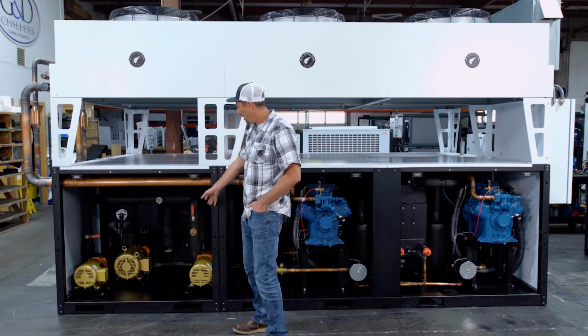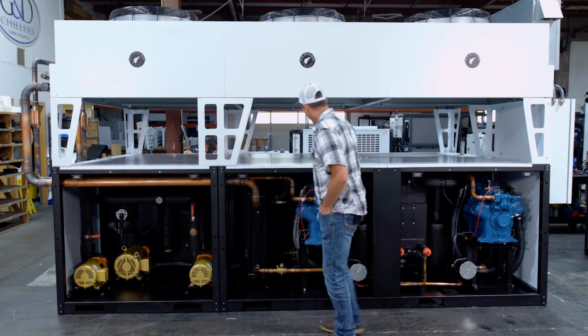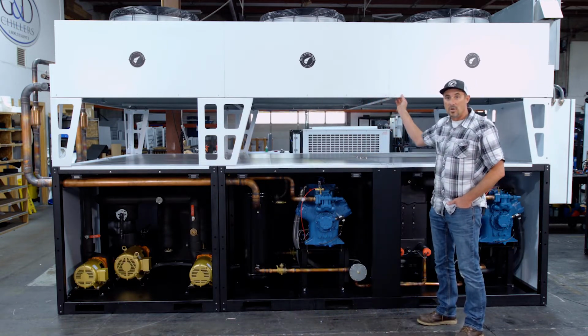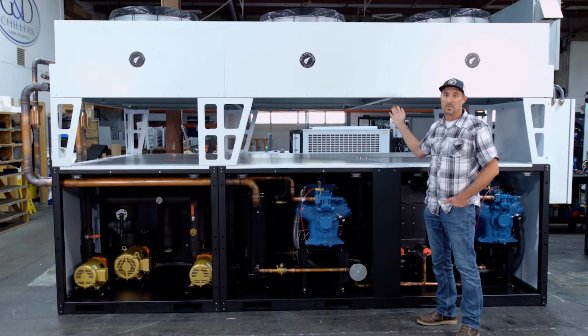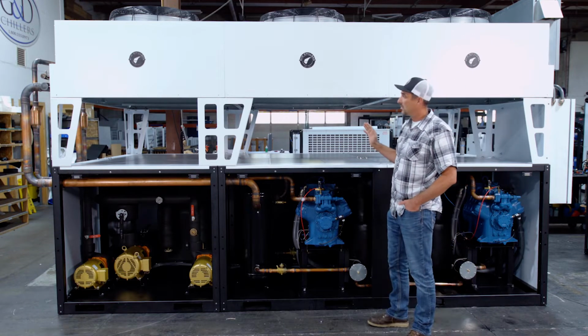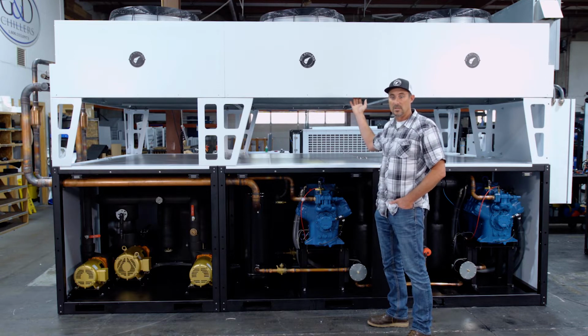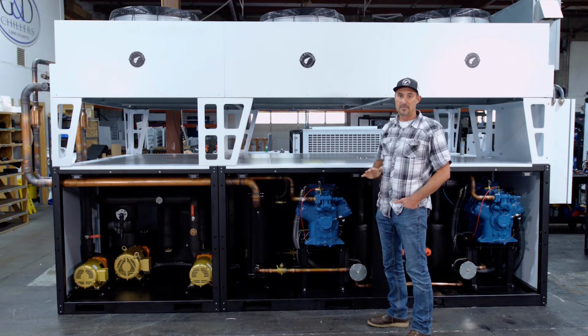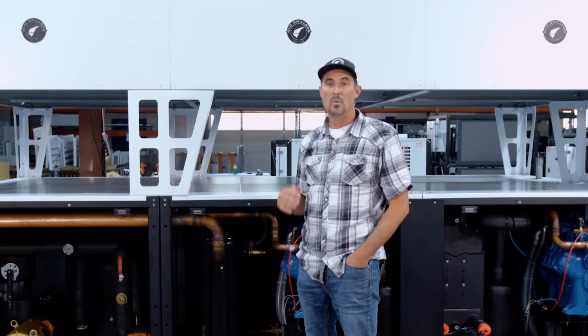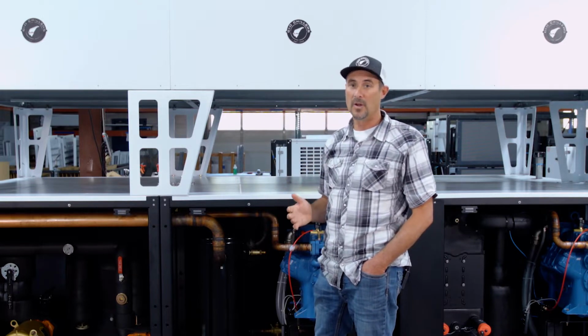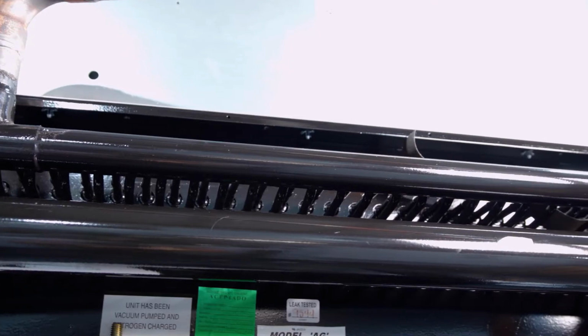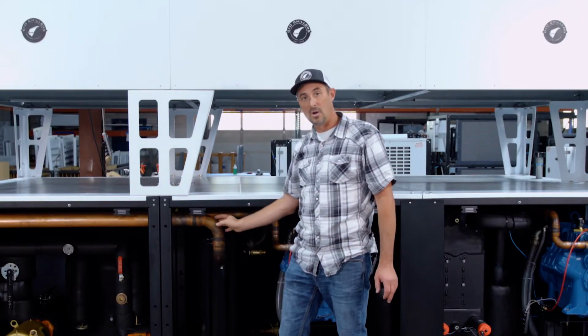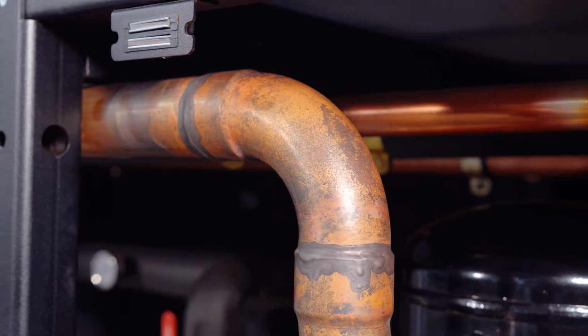You can see these are all high efficient motors, along with a very large and oversized condenser. A lot of our dairy customers are going to be in high ambient areas, and so it's very important for us to have an oversized, large air-cooled condenser to maximize efficiencies during those hot ambient days. We understand that the dairy farm is a very harsh environment. That's why all of our condenser coils are coated with Electrofin coating. Not only is the condenser coil coated, but all of the copper piping is coated as well. We also only use silver solder on all of the joints to prevent any kind of corrosion or leaks in the future.